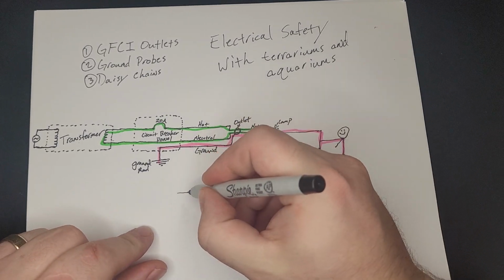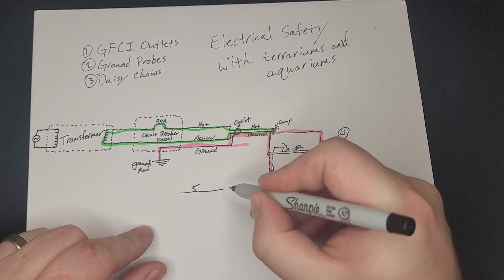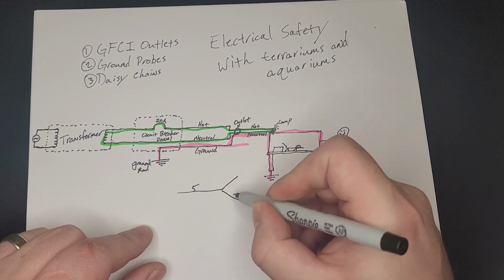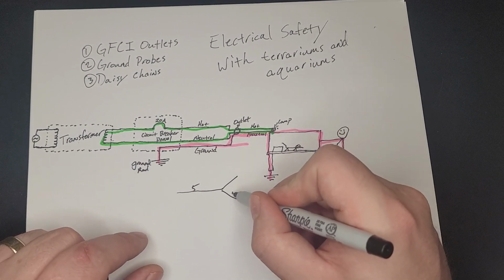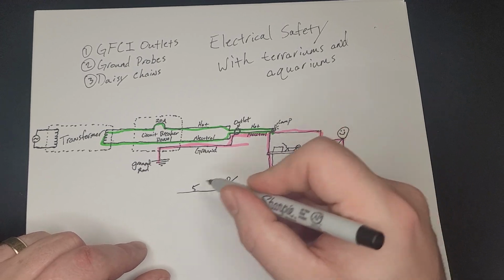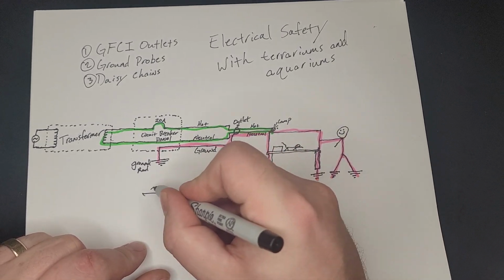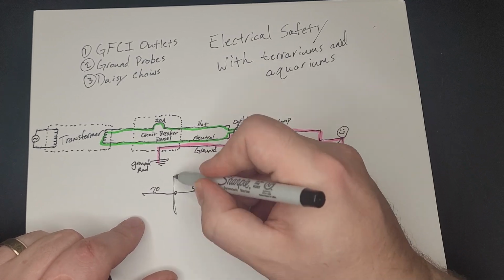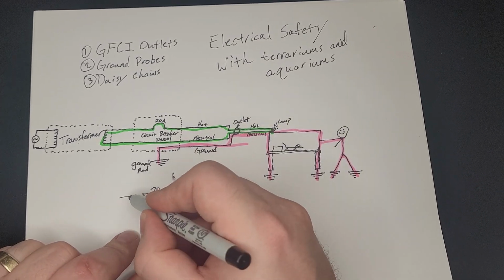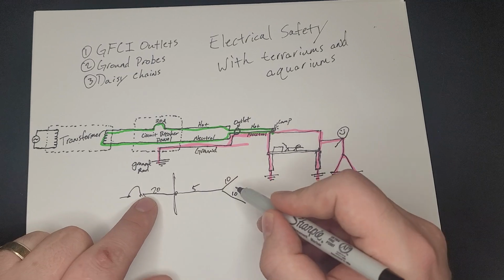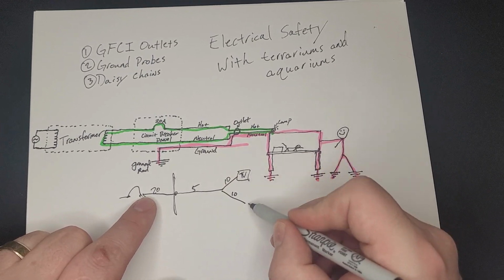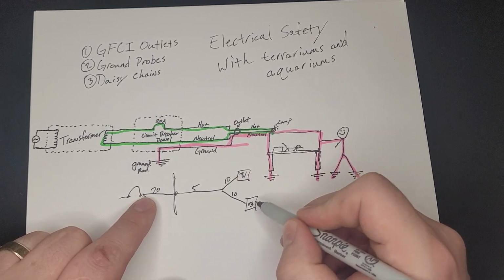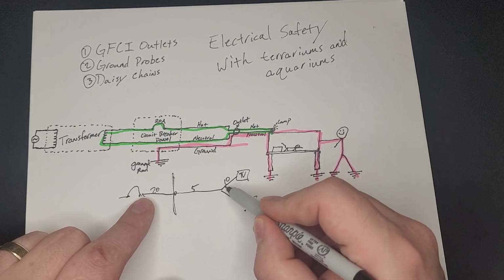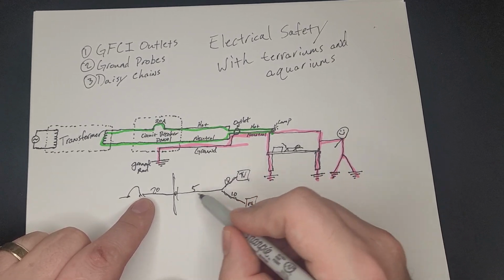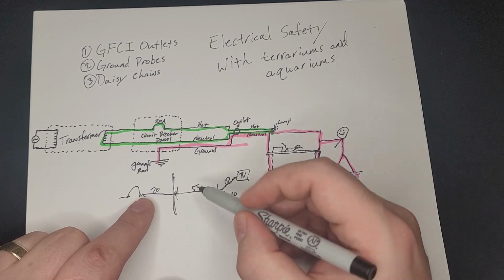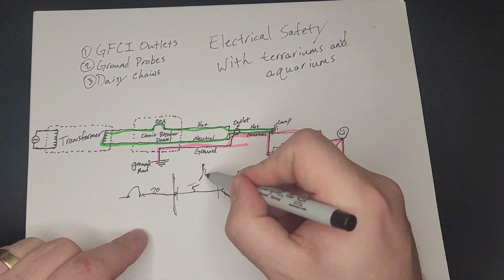Say you have one cord rated for 5 amps, and two other cords rated for something more, say 10 amps. All of this is connected to a circuit providing 20 amps, say at your wall outlet. Your house is fine, the circuit breaker doesn't trip, it's providing 20 amps of current. You've got a bunch of devices on here, a TV and some music player, and you're pulling 20 amps. So this cable is fine, this cable is fine. However, this one, because it's only rated for 5 amps, can heat up and catch fire and burn.